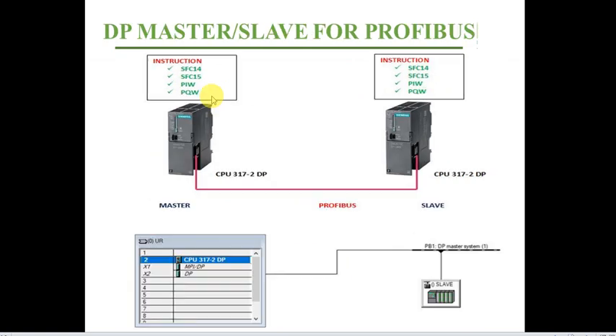The third type is master and slave, where one PLC acts as master and the second acts as slave. The connection is via Profibus, so the two PLCs must have different Profibus addresses. The instructions are also System Function 14 and System Function 15, or you can directly use input word, input byte, output word, or output byte.